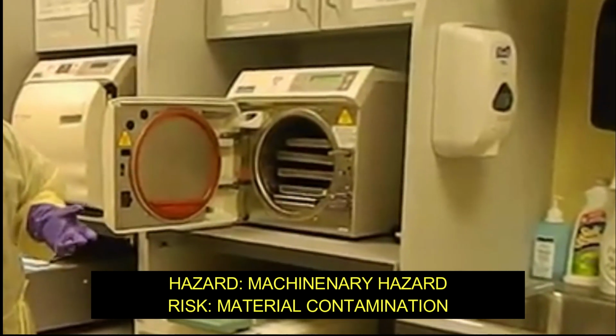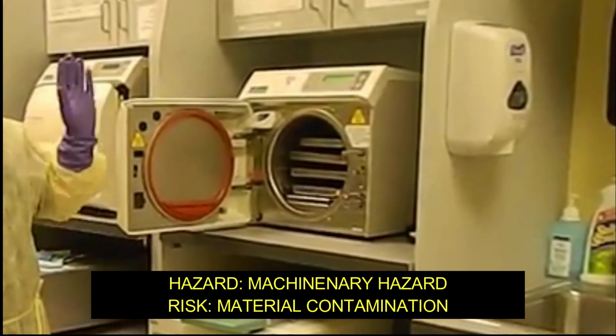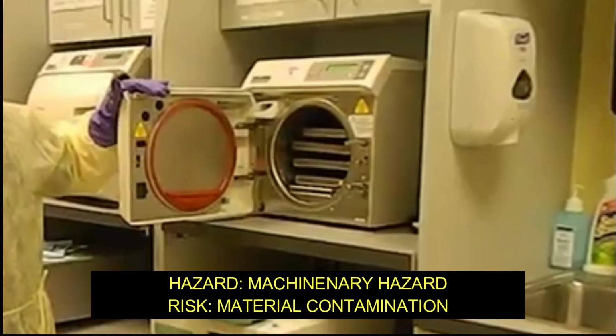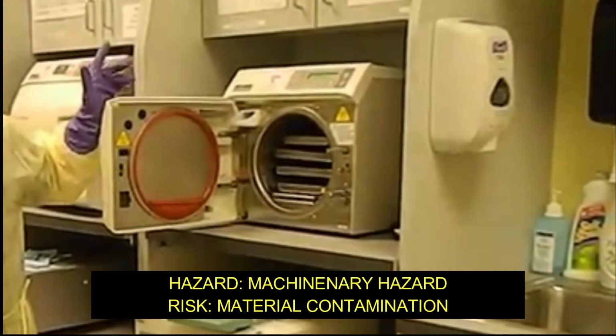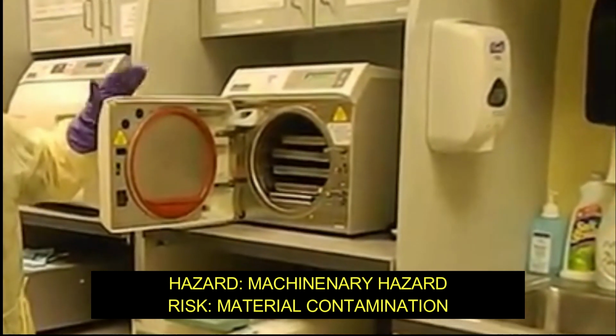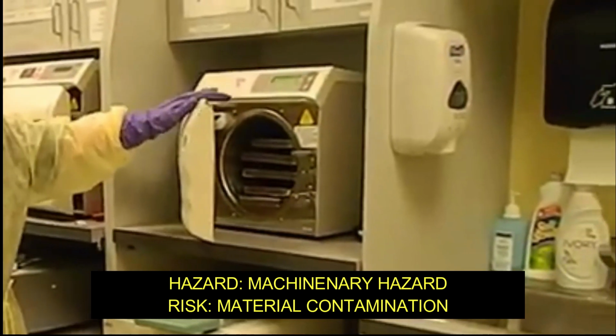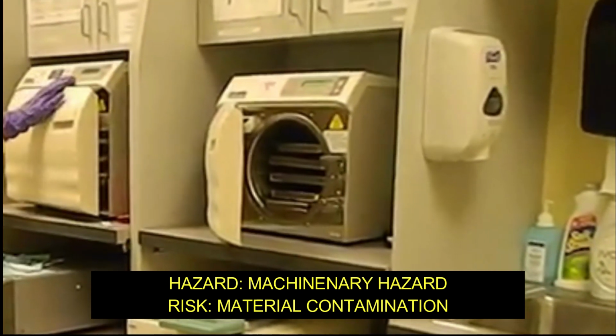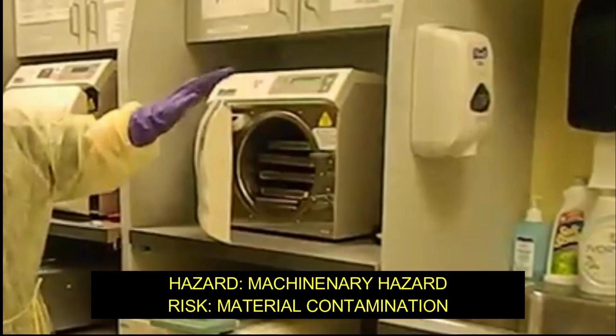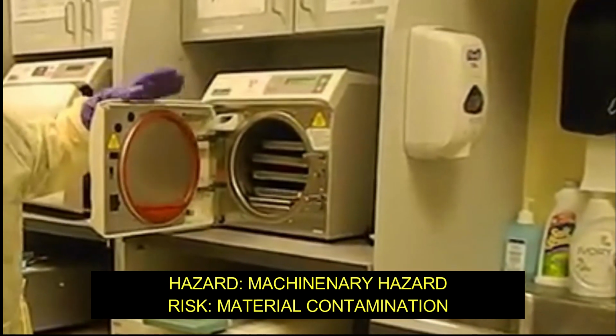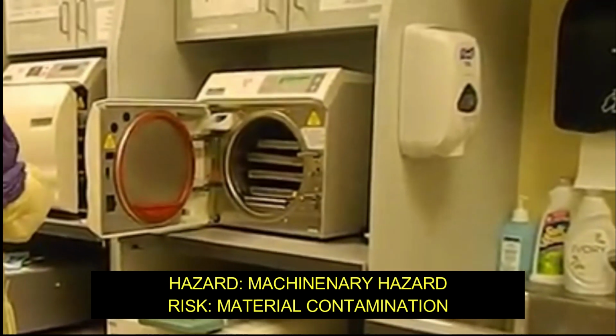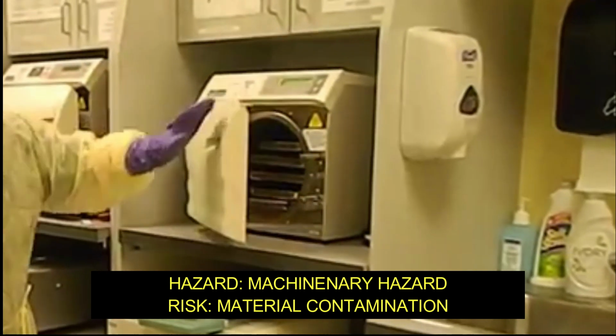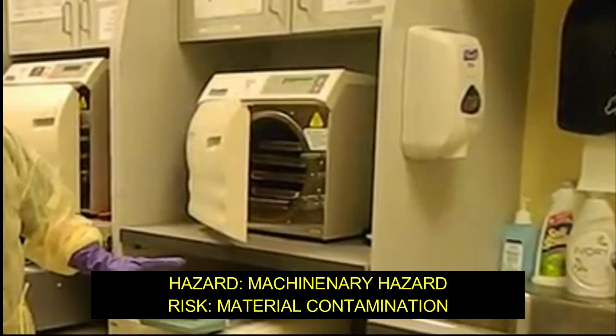Improper packaging can lead to malfunction or damage of the autoclave, resulting in injuries or failed sterilization of materials. The technician must ensure that the packaging materials are autoclave safe, compatible with the contents, and tightly sealed to prevent any leaks. The technician must use autoclave tape or labels to indicate the items have been sterilized and are safe to use. They must also ensure that the autoclave chamber is not overloaded and there is enough space for the steam to circulate around them.